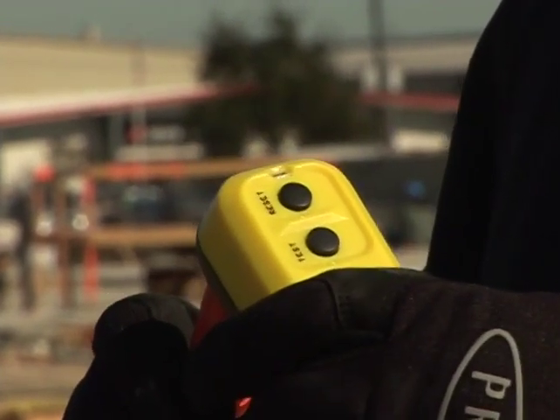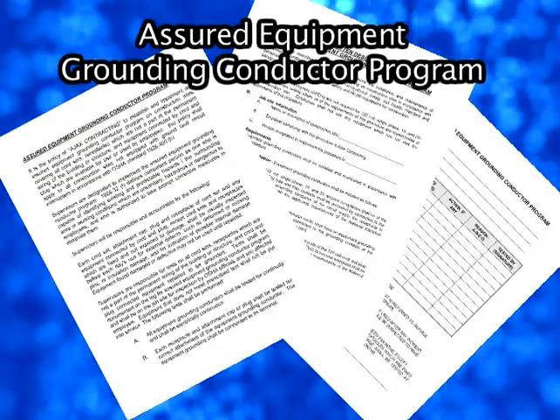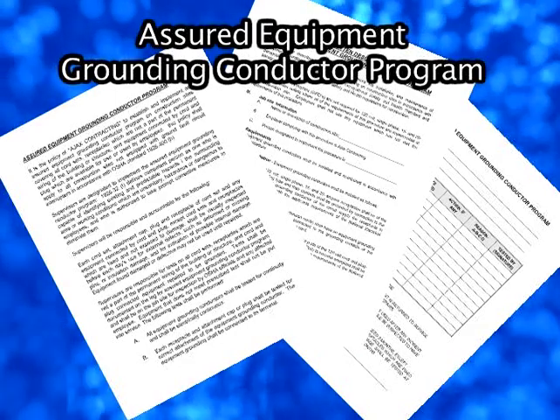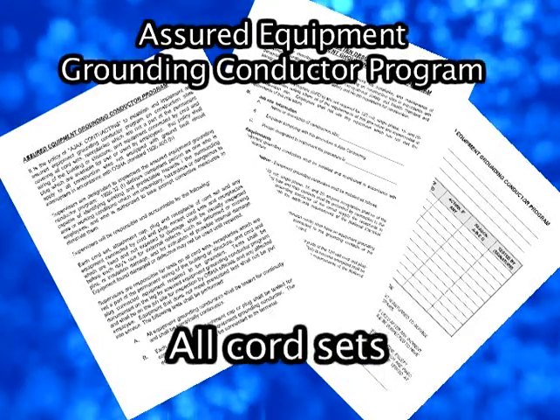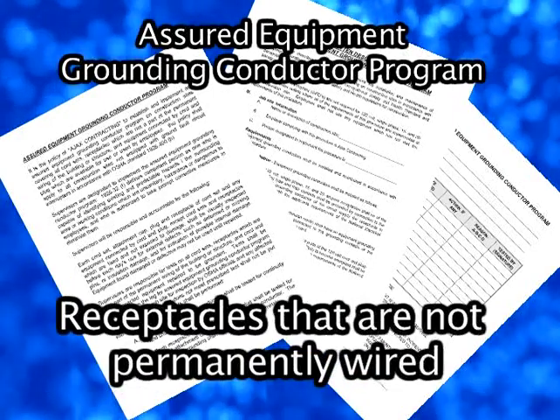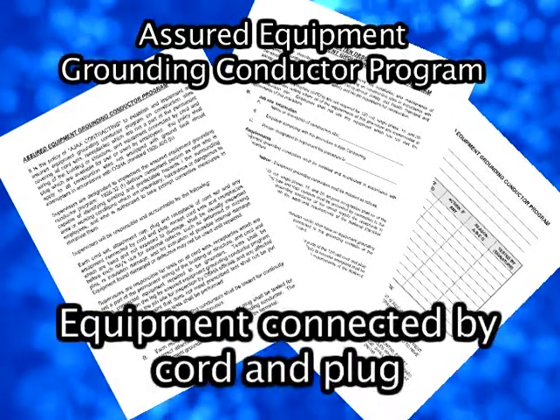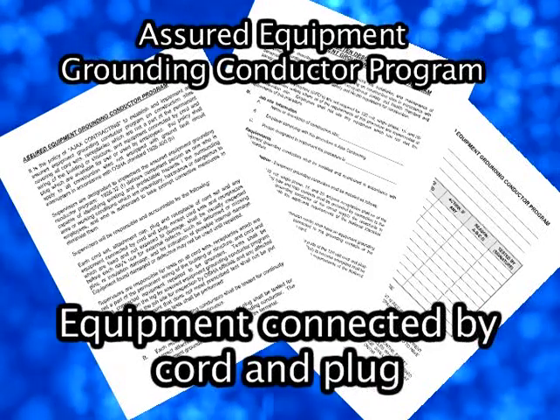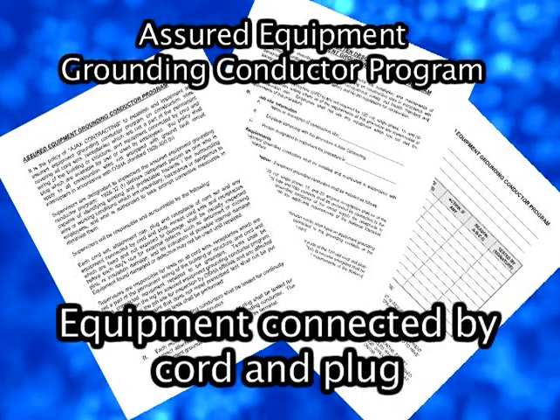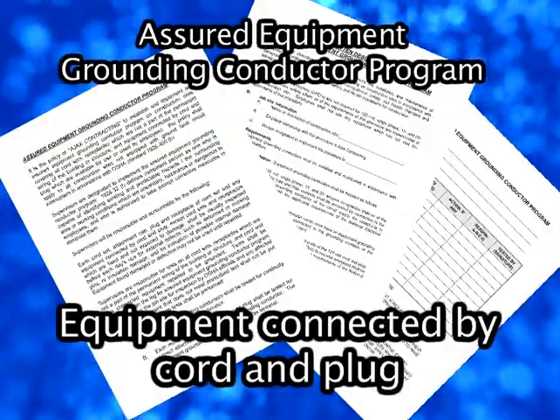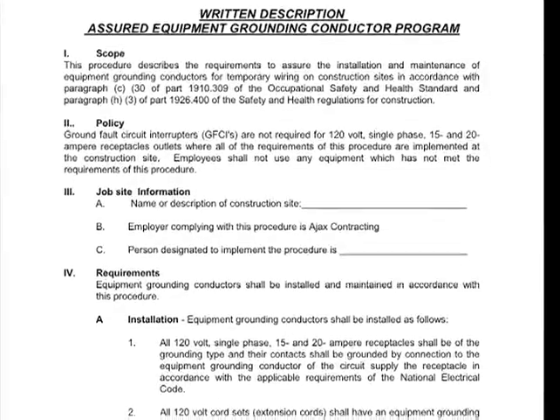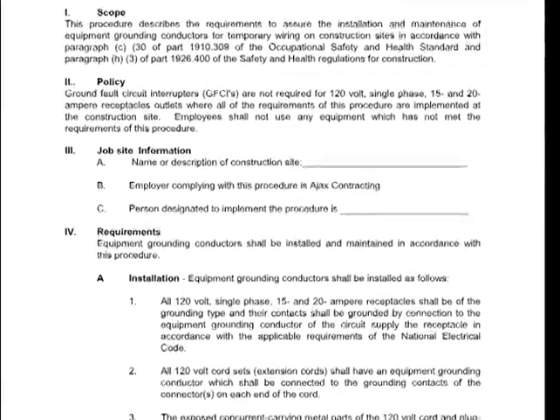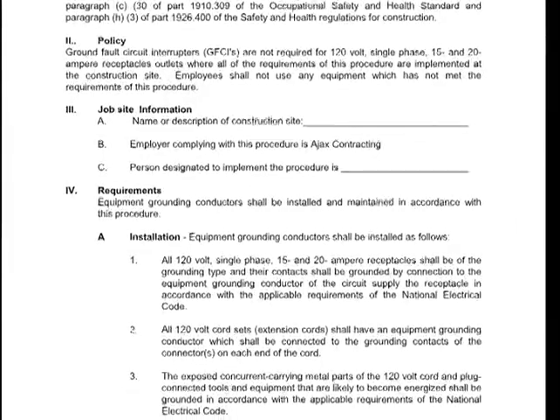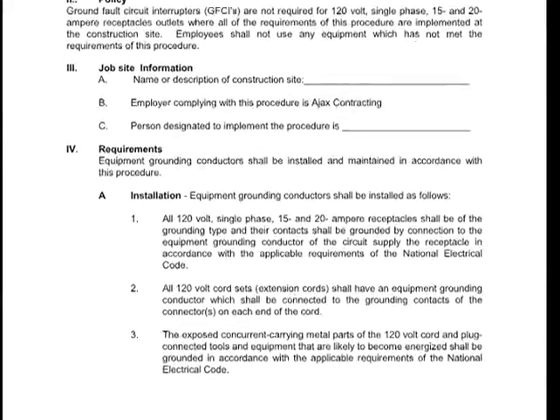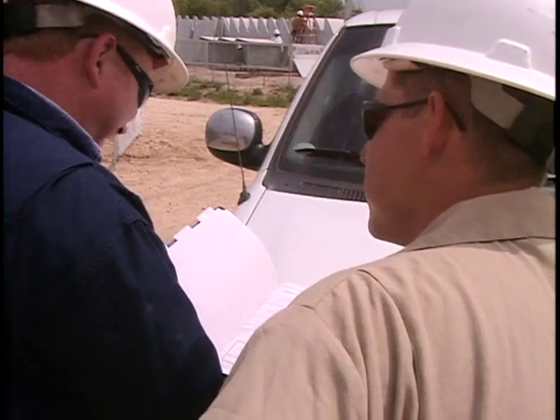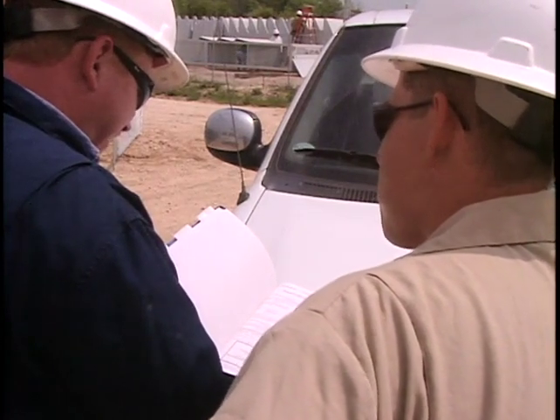general grounding requirements. The Assured Equipment Grounding Conductor program is a written program covering all cord sets, receptacles that are not part of the permanent wiring of the building or structure, and any piece of equipment connected by cord and plug that is available for use or used by workers. A written description of the program must be kept at the job site outlining specific procedures for the equipment inspections, tests, and test schedule, and made available to OSHA and to all affected persons on demand.